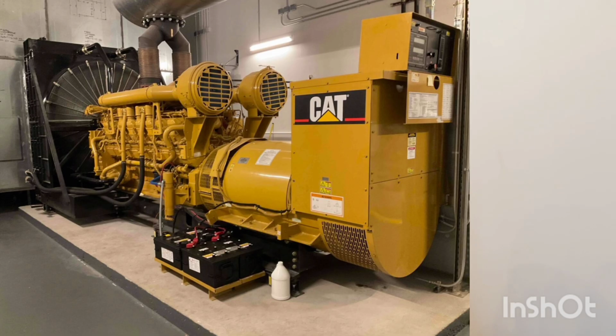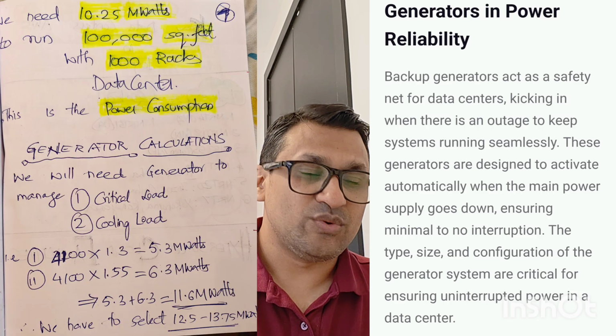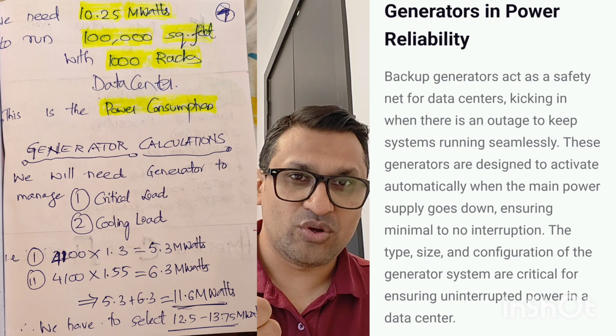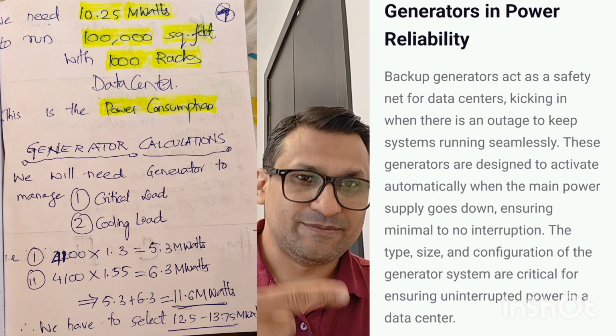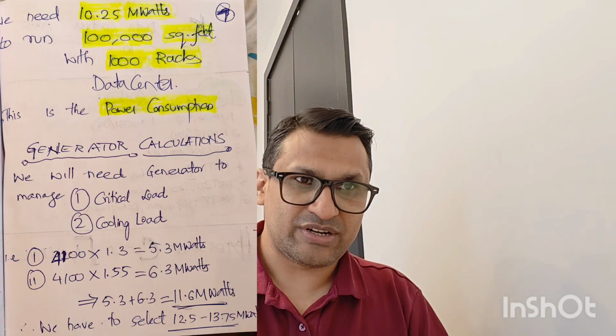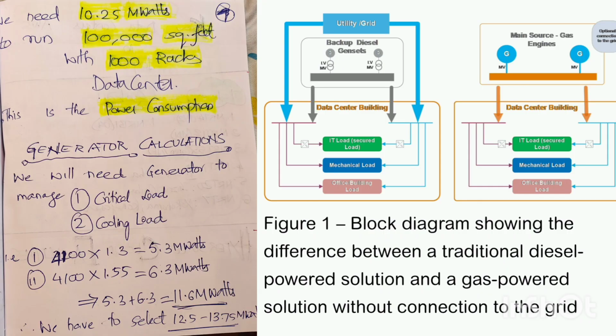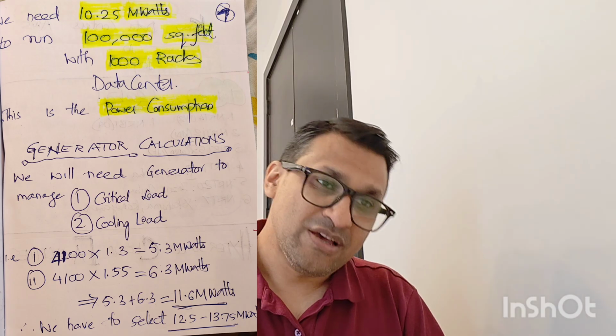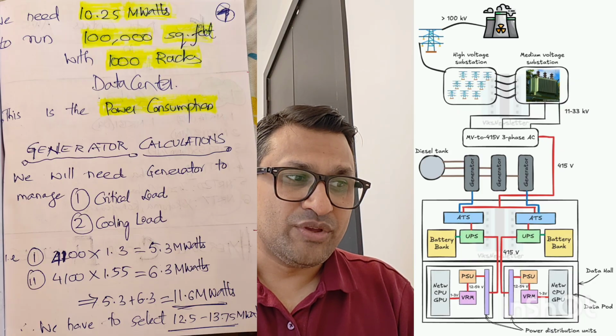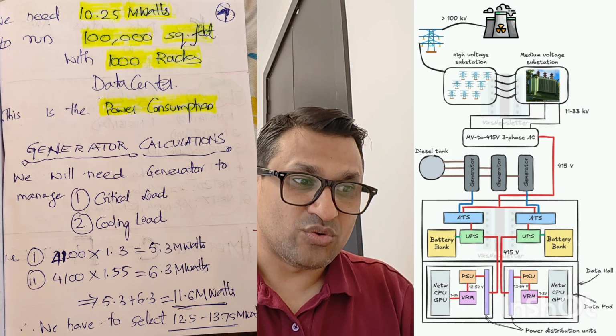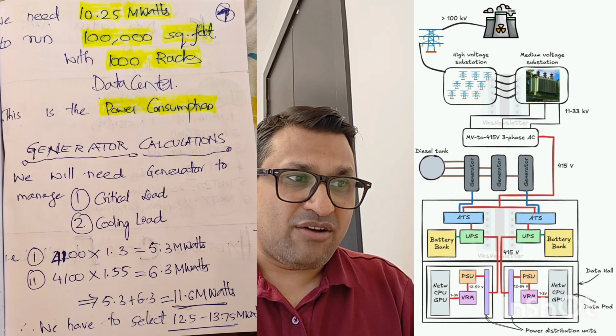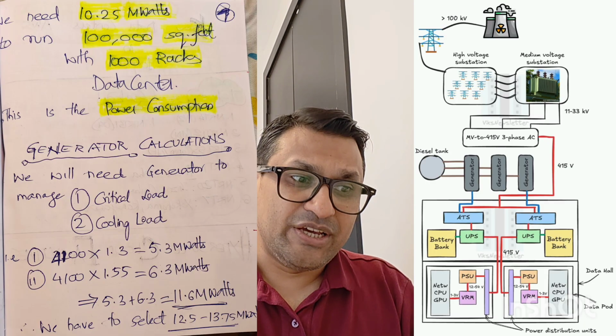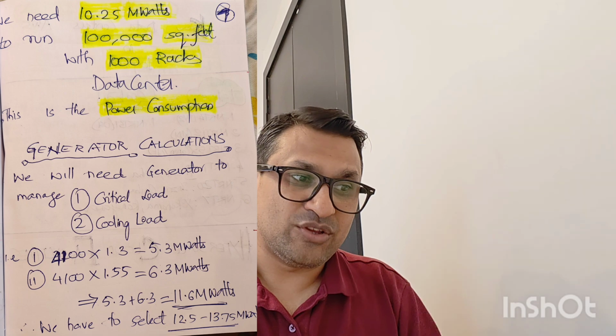So for generator calculations, what is the size of generator required? Obvious question. We need a generator to manage 2 loads, the critical load and the cooling load. The critical load is from the servers, racks, lighting, the items which keep the data center running. And then the cooling load: you need a mechanical system which runs and cools the systems. So we need the generator to manage these 2. The critical load is 4100 and the cooling load is 4100.